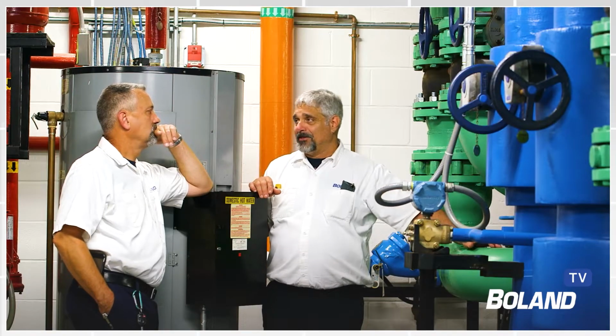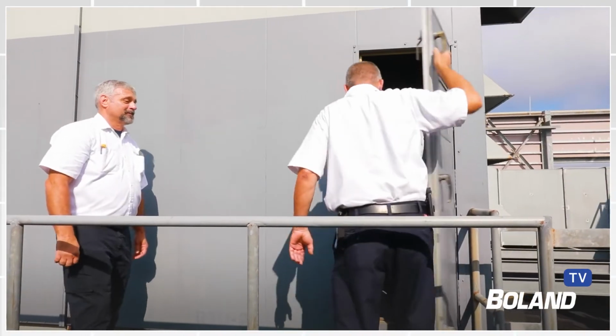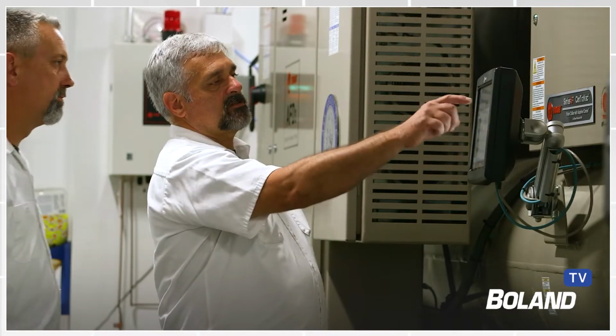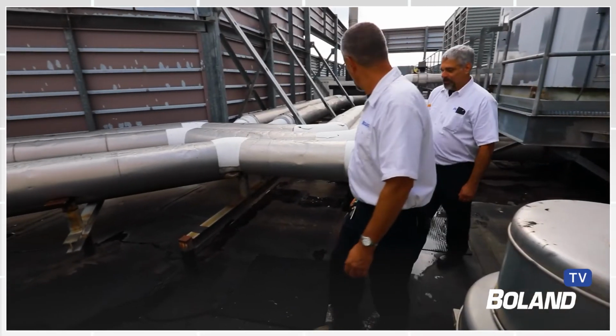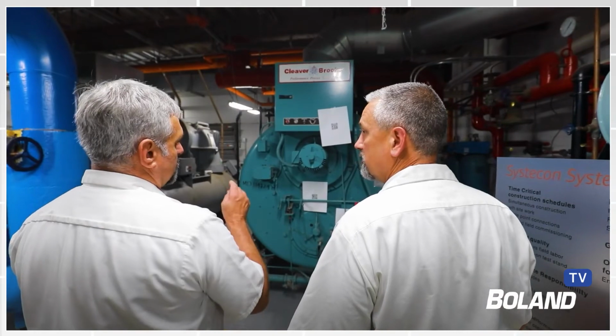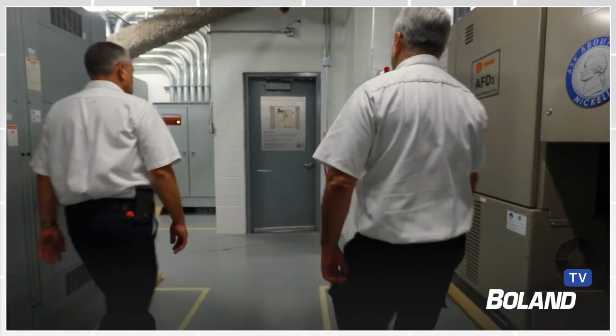Going into the spring, it's important to clean out and check all of the water treatment tubing that the chemical goes through, checking the pumps, making sure everything is in working order. It's always a good idea to start out the season, if you haven't run a cooling tower or chiller for a while, to shock the system with 2 parts per million of free chlorine to get ahead of any bacteria.